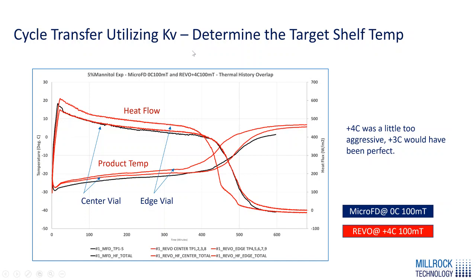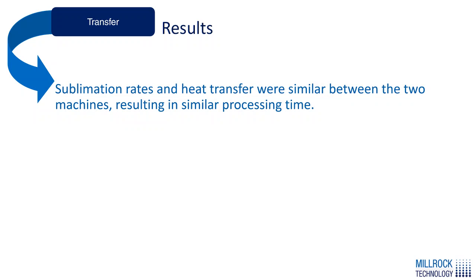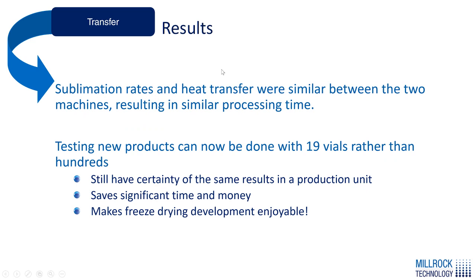This is significant because it means we can take the protocol developed in the laboratory and transfer it into production and get the same results. We determined the end of primary drying using the capacitance manometer versus the Pirani, and primary drying times were within minutes of each other between the two systems. The sublimation rates and heat transfer were similar between the two machines when we changed the shelf temperature, resulting in similar processing times. Testing new products can now be done with anywhere between 3 and 37 vials, and we can use that information for transfer.